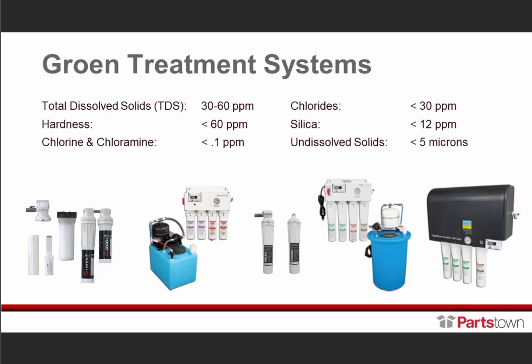Here are a few of our Groen water quality treatment systems. These are our water quality standards: 30 to 60 parts per million on total dissolved solids, hardness less than 60, chlorine/chloramine less than 0.1, chloride less than 30, silica less than 12, undissolved solids less than 5 microns, and pH needs to be between 7 and 9. If it gets below 7, the water actually becomes corrosive.